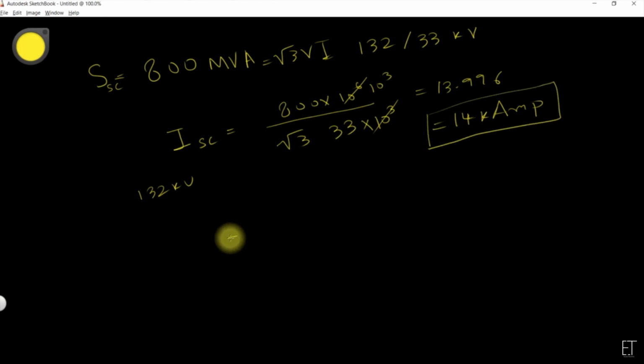In the same way, if you supply at the low voltage side and the HV side is short circuited, I short circuit HV, this is LV. So for HV we just have to change here 800 MVA divided by under root 3 into 132. So it will be equal to 800 divided by 1.732 divided by 132, which is almost equal to 3.5 kiloamperes. So this is the case when the LV side has a source and HV is short circuited.